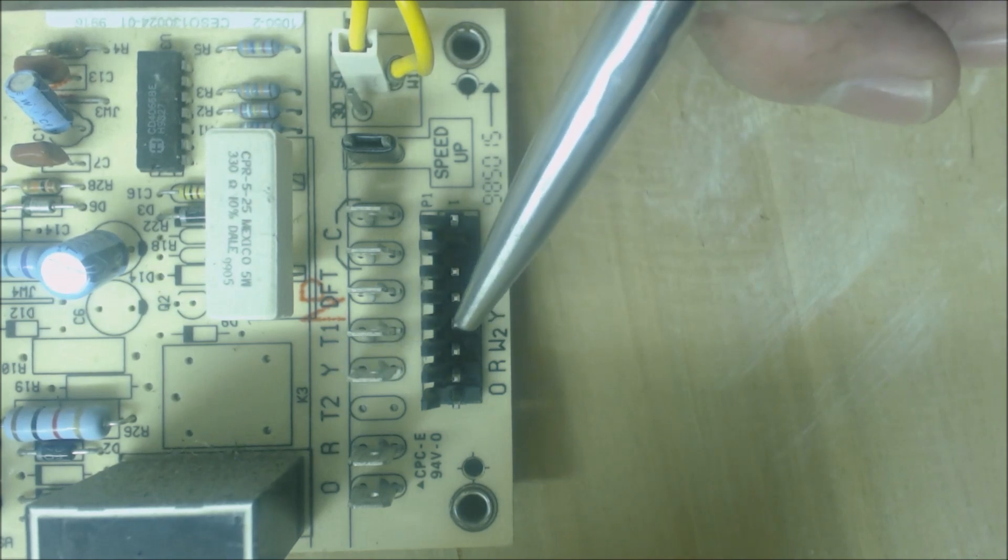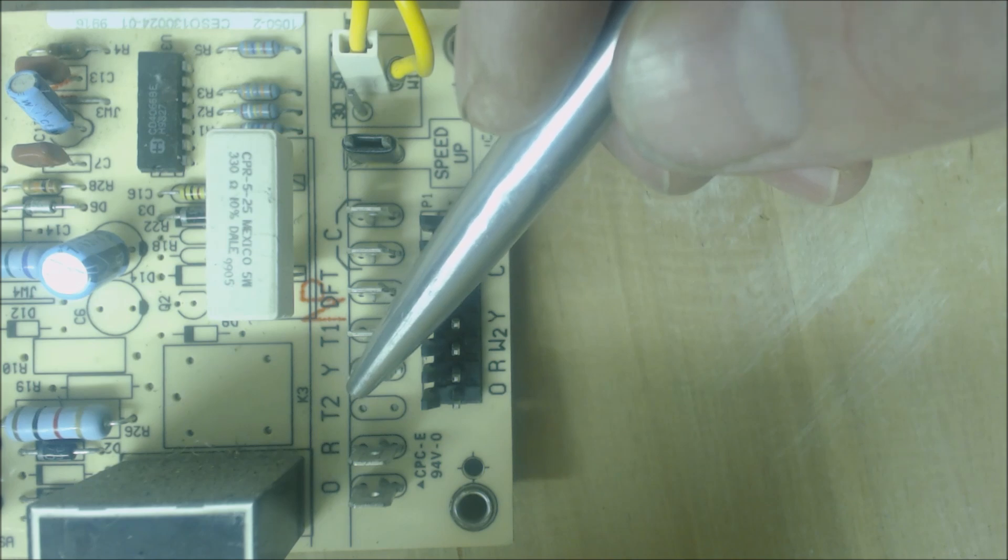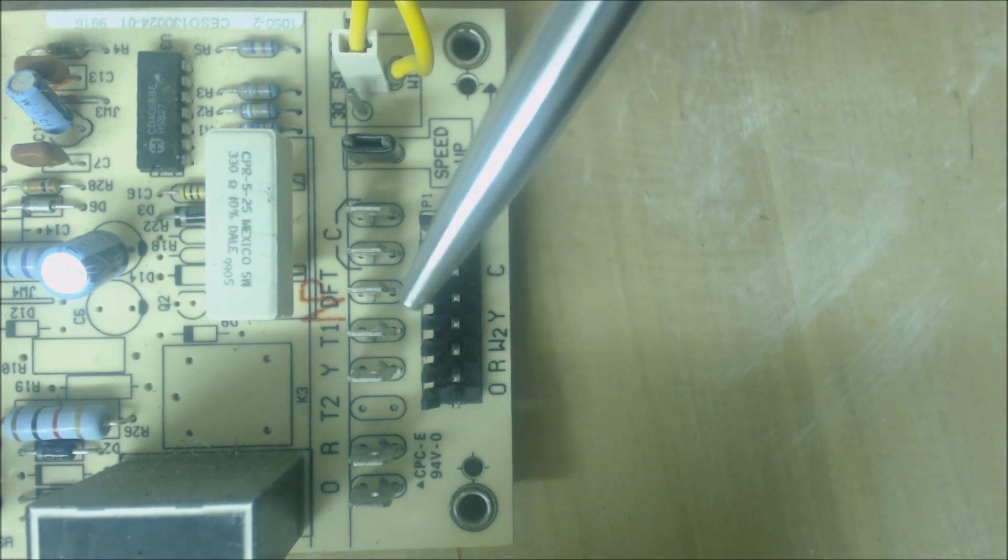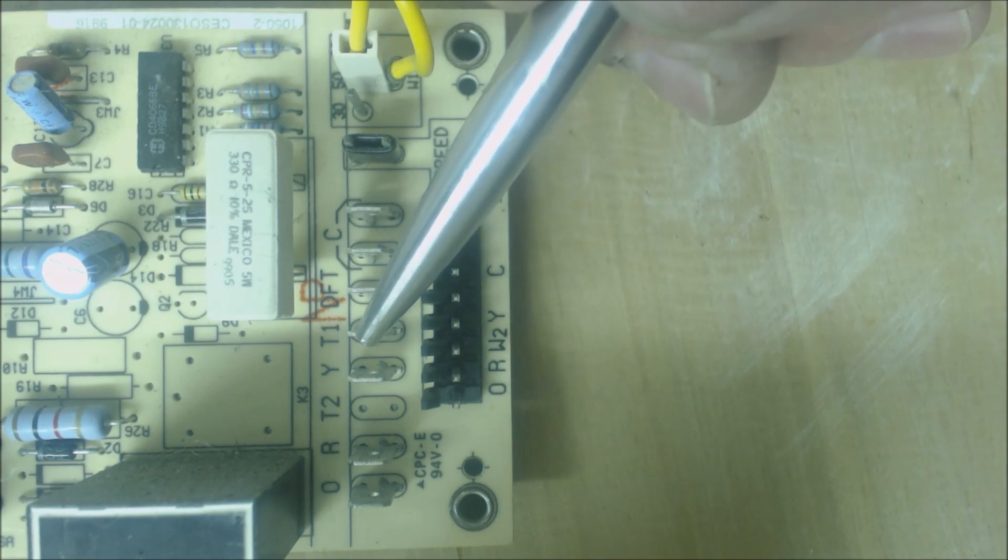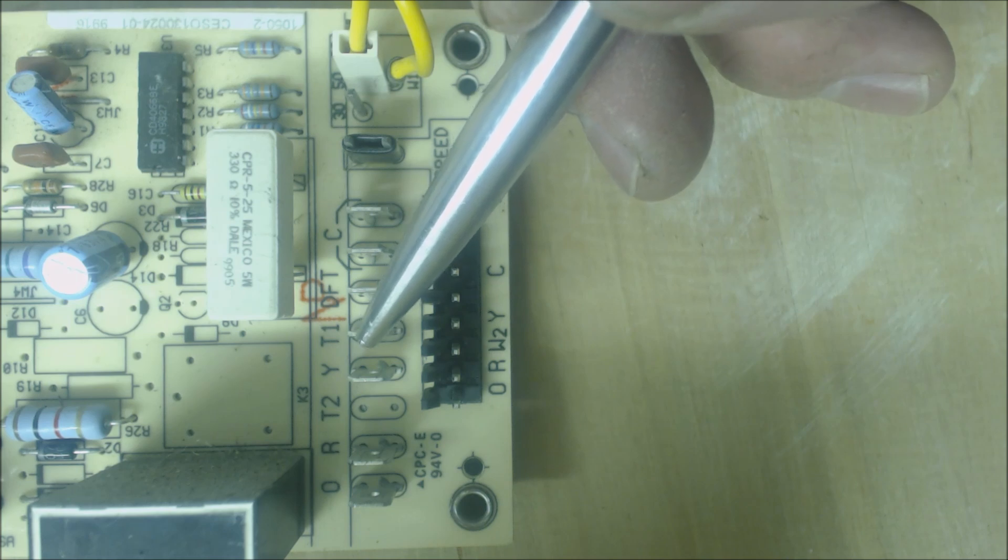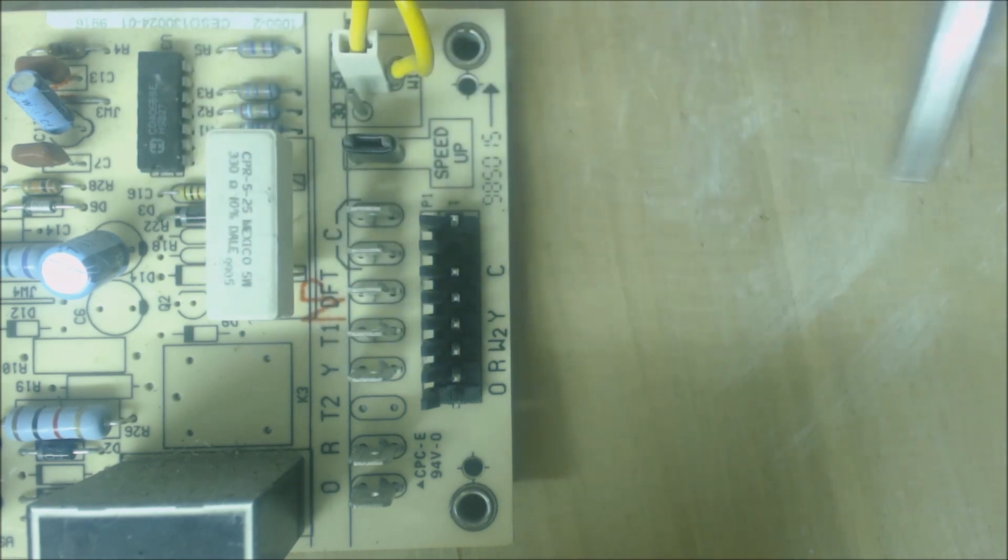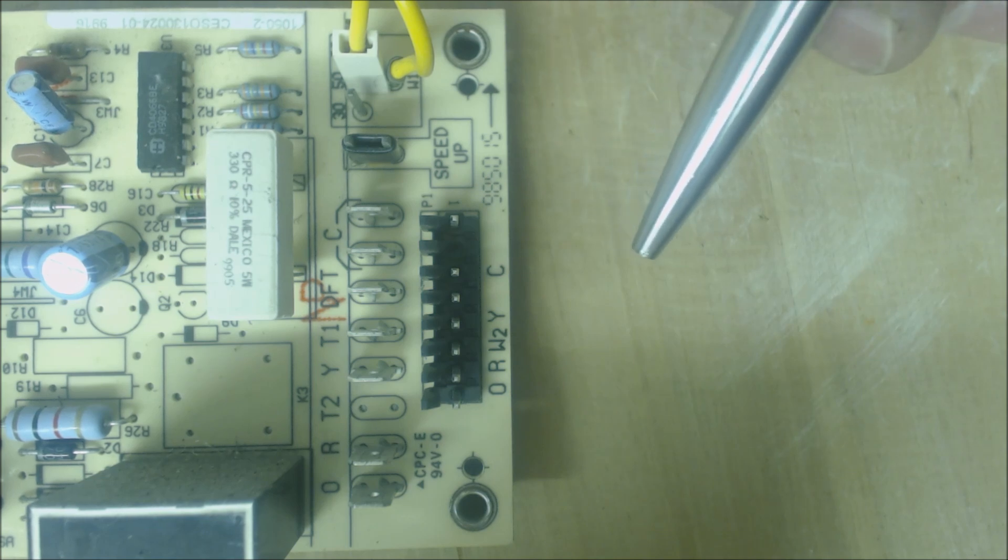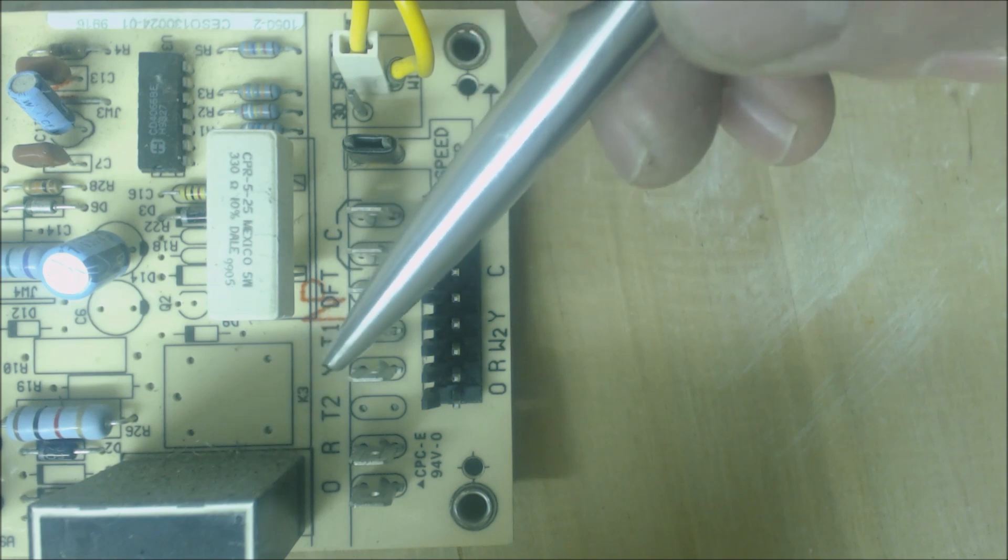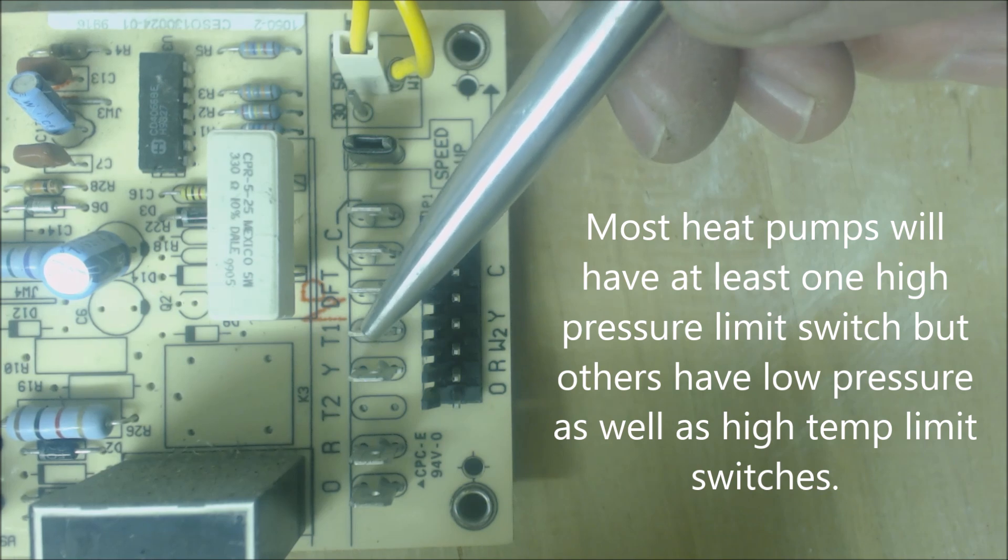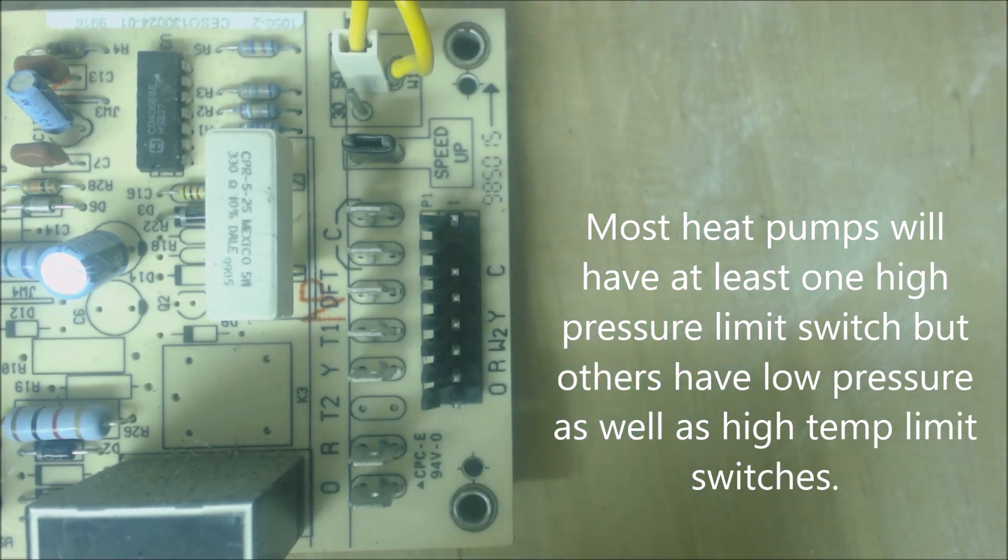Y is jumpered from here, from the source right here, coming over to here, and then it goes through the high pressure and temperature limit controls as well as any low pressure controls. Then it comes back in to T1. Once T1 has a signal, 24 volts, the control board knows that all of those pressure temperature safety switches are intact and closed.